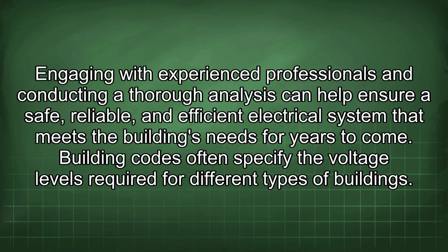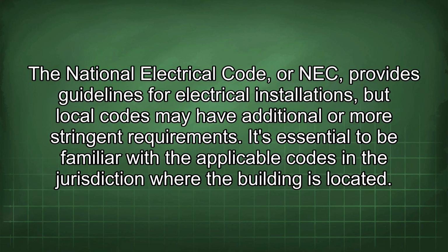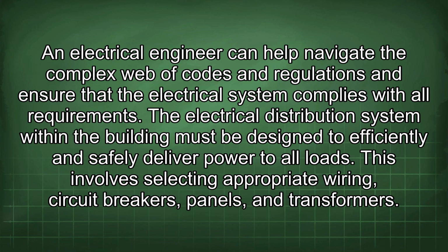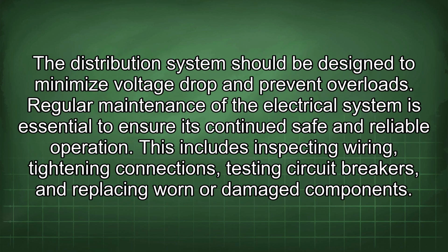Building codes often specify the voltage levels required for different types of buildings. The National Electrical Code, or NEC, provides guidelines for electrical installations, but local codes may have additional or more stringent requirements. It's essential to be familiar with the applicable codes in the jurisdiction where the building is located. An electrical engineer can help navigate the complex web of codes and regulations and ensure that the electrical system complies with all requirements. The electrical distribution system within the building must be designed to efficiently and safely deliver power to all loads. This involves selecting appropriate wiring, circuit breakers, panels, and transformers. The distribution system should be designed to minimize voltage drop and prevent overloads.